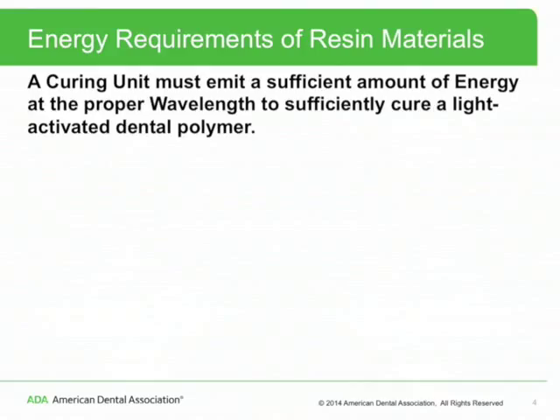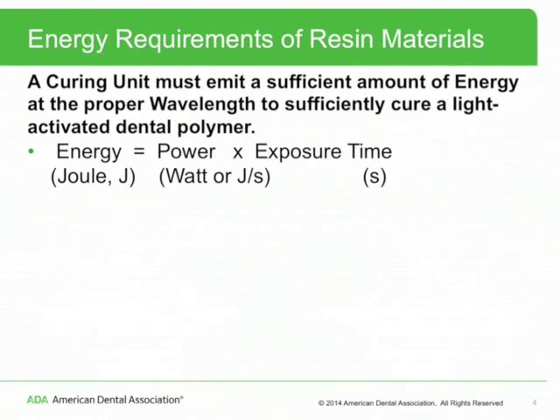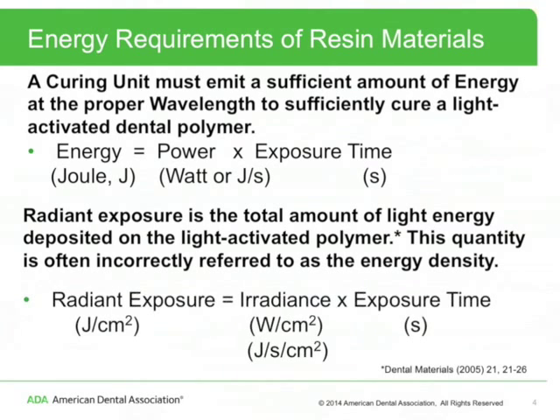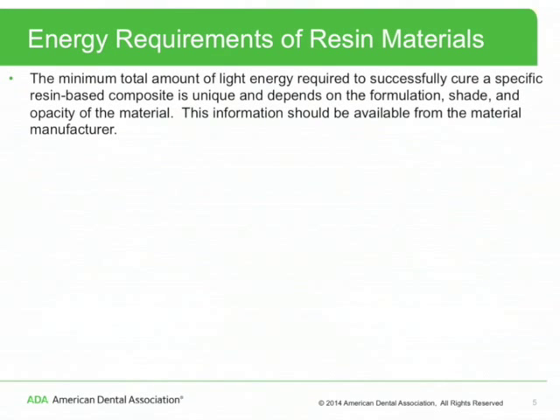What is the proper wavelength will be discussed later. Energy expressed in joules is equal to power times exposure time. Radiant exposure is the total amount of light energy deposited on the light-activated polymer — though this quantity is often incorrectly referred to as energy density. Radiant exposure is expressed in joules per square centimeter and is equal to irradiance times exposure time. The minimum total amount of light energy required to successfully cure a specific resin-based composite is unique and depends on the formulation, shade, and opacity of the material.